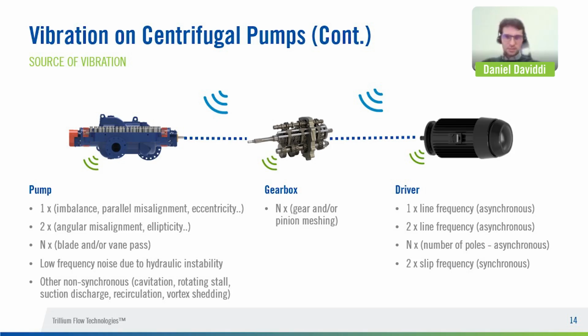The nx refers to the vibration caused by the interaction between the pump blades or vanes, so a vibration that occurs at multiples of the rotational speed, typically the number of blades or vanes. We also have low frequency noise, represented by subsynchronous vibration and caused by fluctuation in the fluid, and finally other non-synchronous sources that come from other hydraulic problems, for example cavitation, rotating stall, suction and discharge recirculation, vortex shedding, and so on. If we have a gearbox, we also have the nx vibration caused by the number of teeth, so the meshing of gear and pinion.